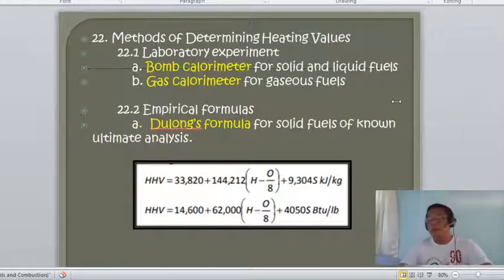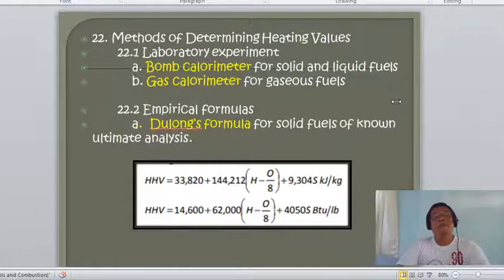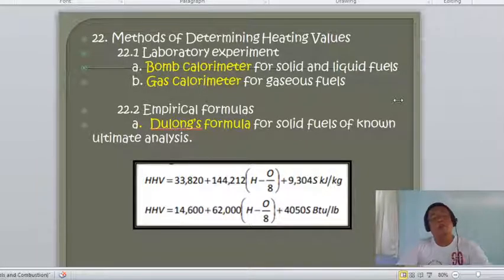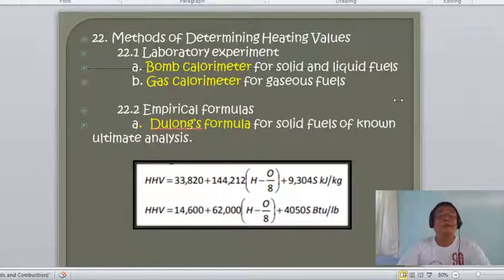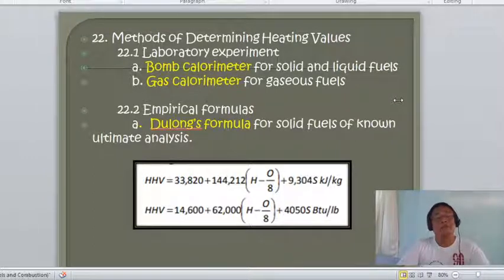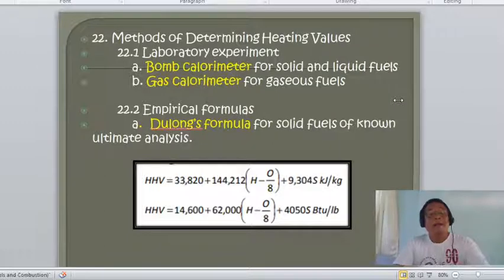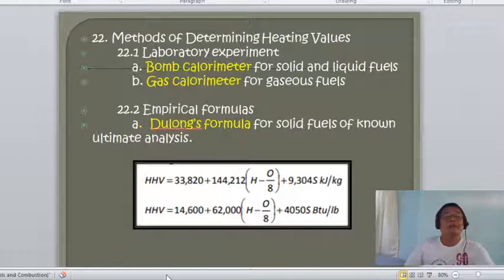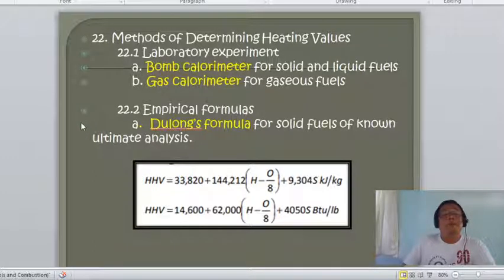There are two methods for determining heating values: the bomb calorimeter, used for solid and liquid fuels, and the gas calorimeter, used for gaseous fuels. We also have Dulong's formula — an empirical formula used with the ultimate analysis of fuel. The higher heating value is: HHV = 33,820 × C + ..., where 33,820 kJ/kg is the heating value of pure carbon.